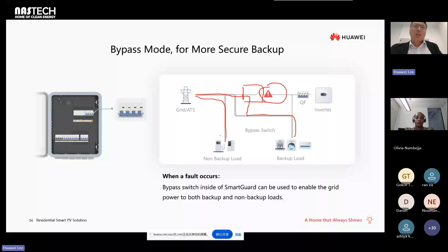And next, we also support DG scenarios. You need an ATS for the DG backup. The ATS connects to the Smart Guard, and when the grid is off, the ES discharges to the load. But when the ES SOC is less than 25%, the DG starts. When the grid is off, the ATS is not switched to the DG side automatically. It is only based on our SOC being less than 25%. It sends the signal to the ATS to switch to this side, and the DG starts working.